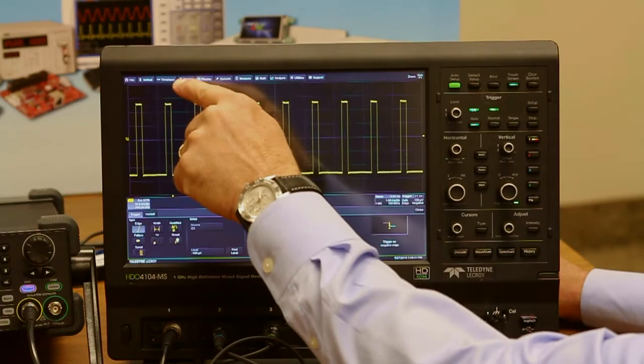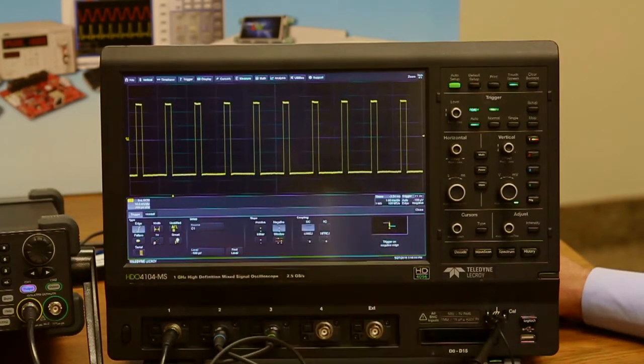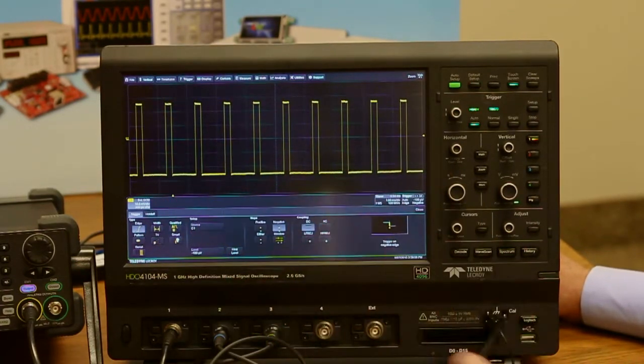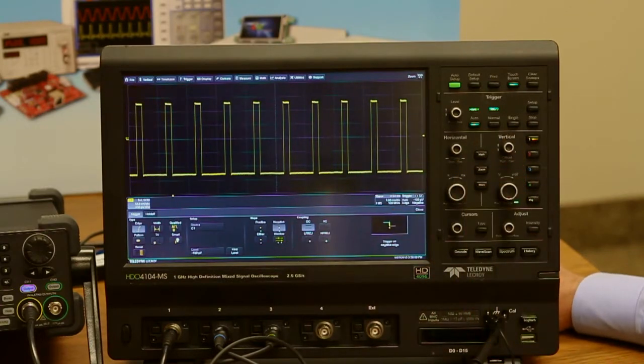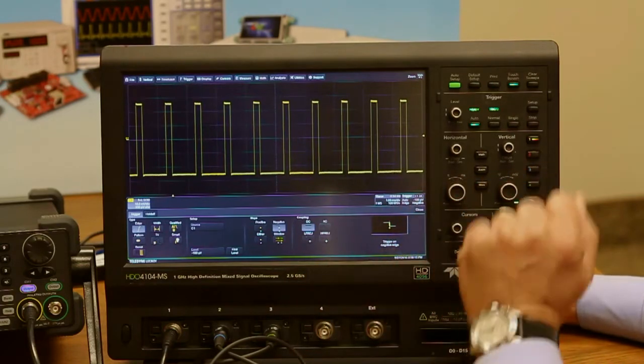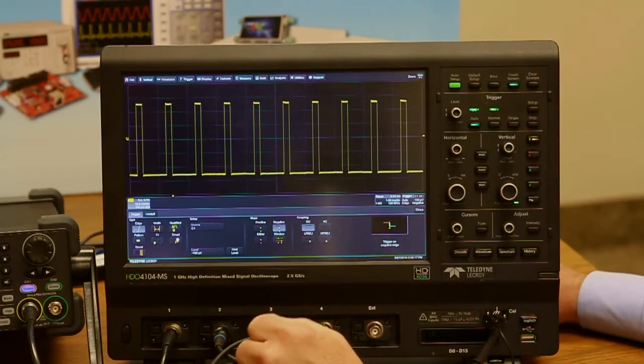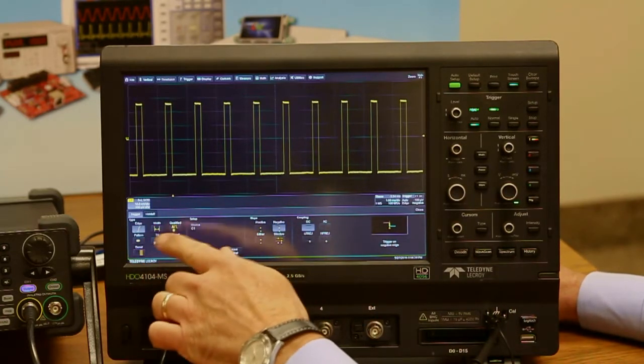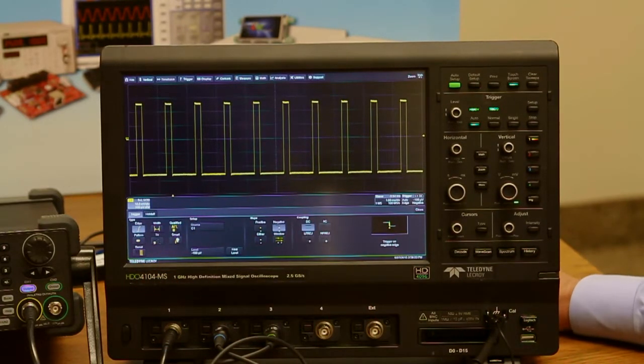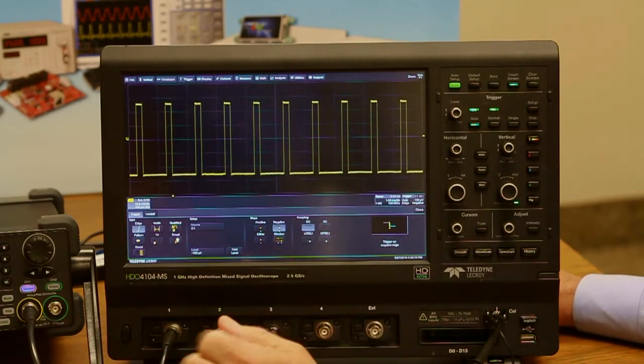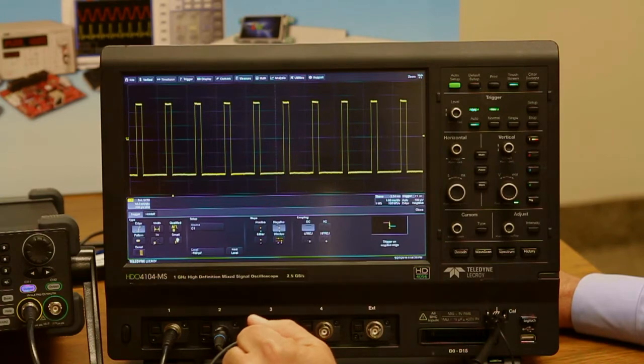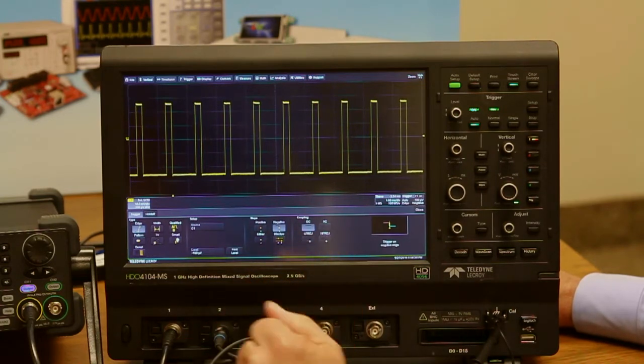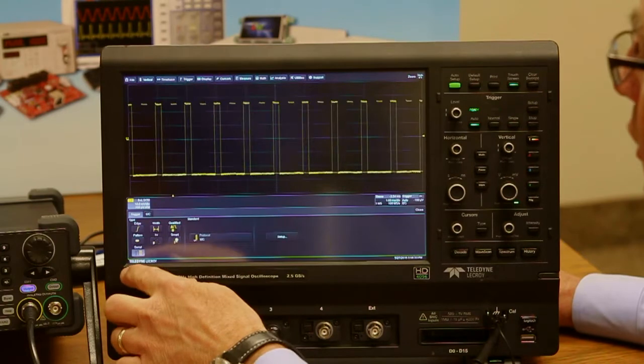Display the trigger dialog section from the pull-down menu. So three ways to access it. You'll choose which one you like and what you're most comfortable with. Again, I just like touching the trigger descriptor and it brings me right to the trigger dialog. So all the triggering you need is right here, whether it be simple edge trigger with or without hold off and qualified trigger, triggering on one channel but only after you've seen something else occur in another.